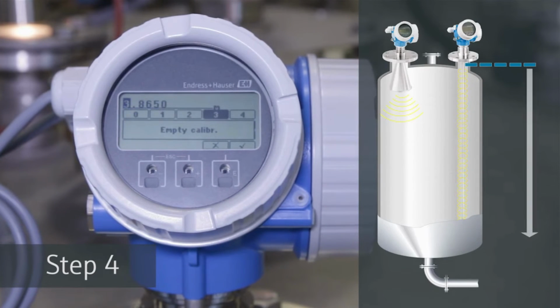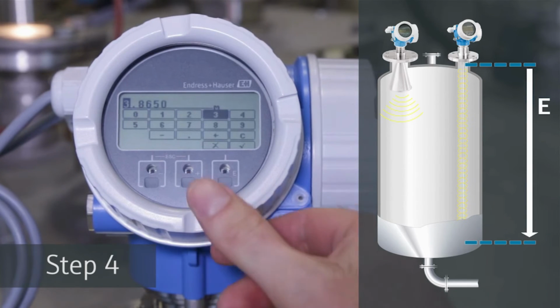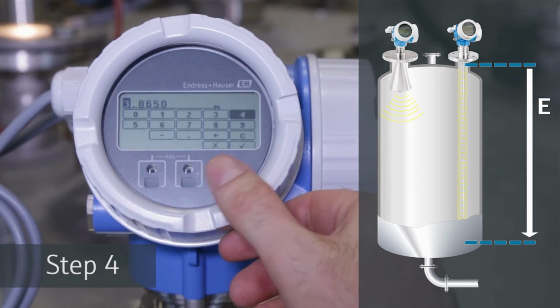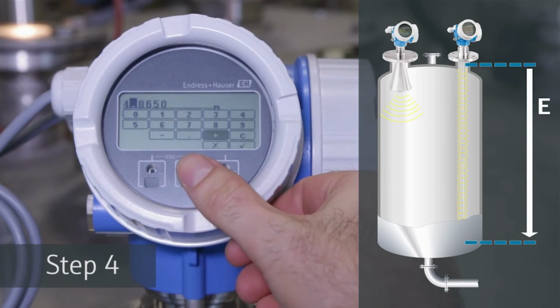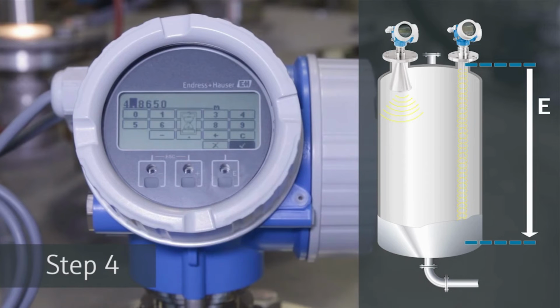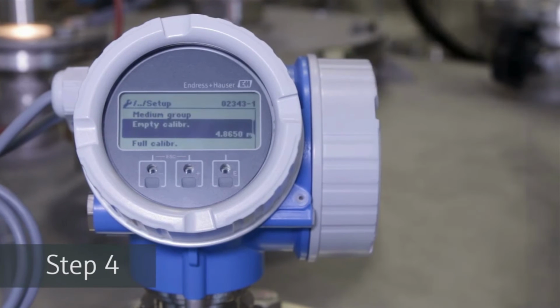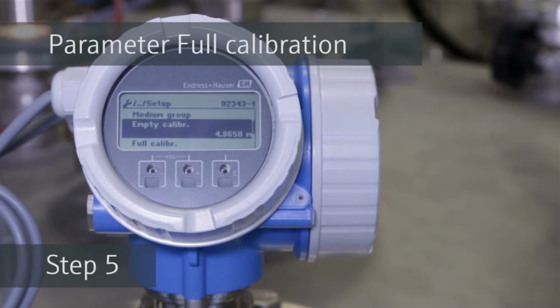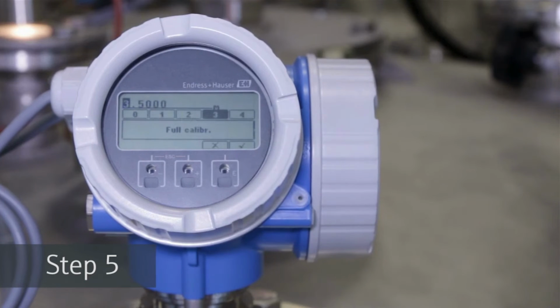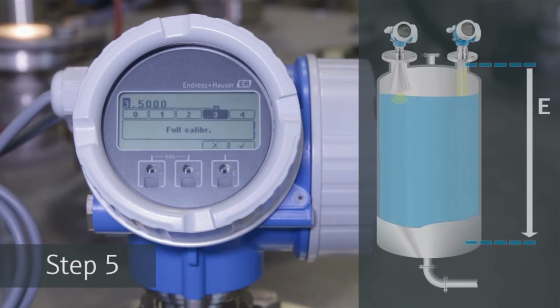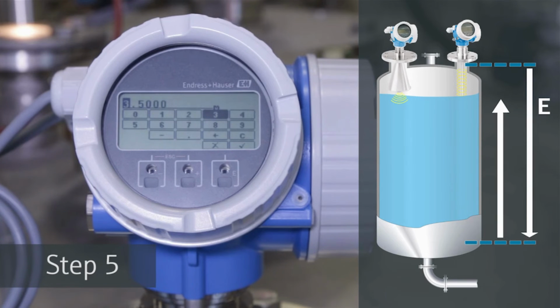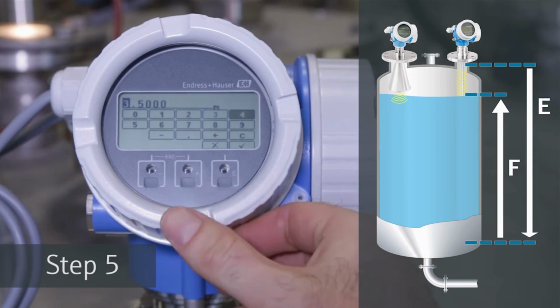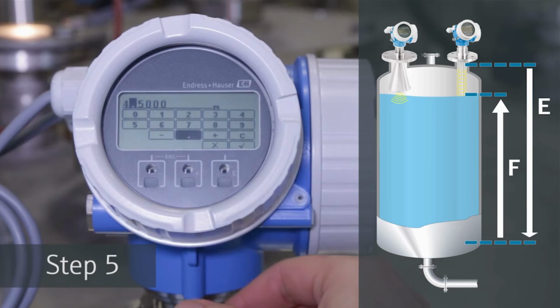The empty calibration, E, determines the distance between the reference point, in our example the lower edge of the flange, and the minimum level. In our case, we select an empty distance of 4.865 meters and confirm with the E key. Determine the full distance F in the parameter full calibration, defined as the distance from the minimum to the maximum level. In our example, we select a span of 3.5 meters.